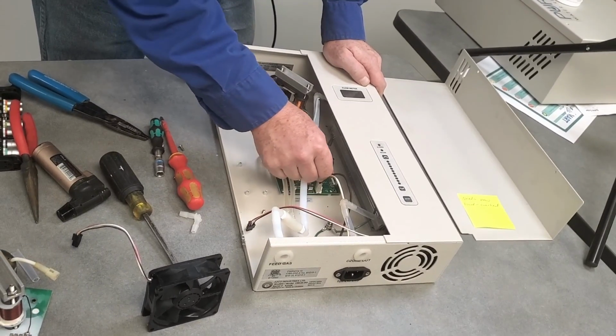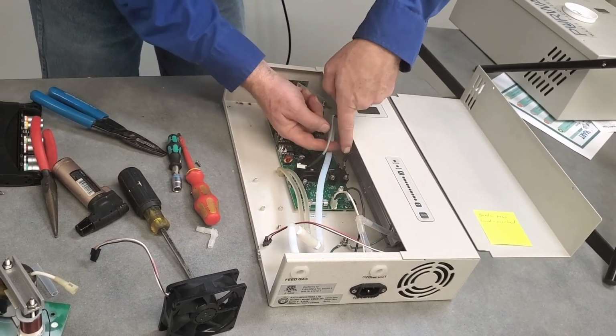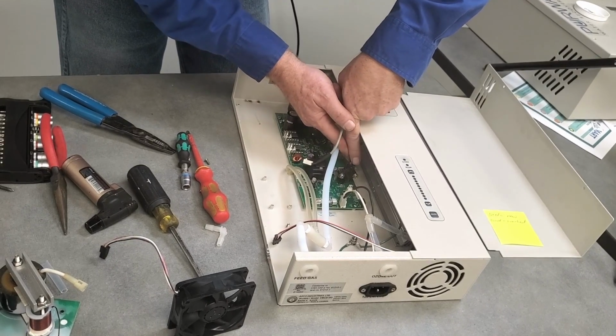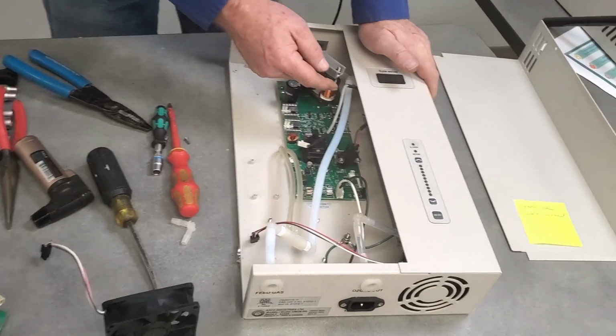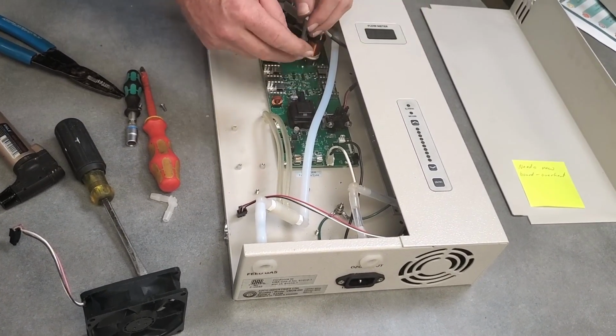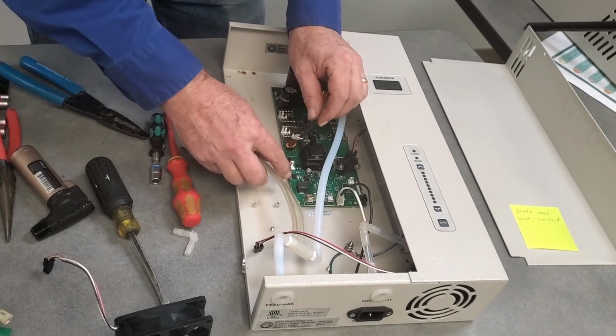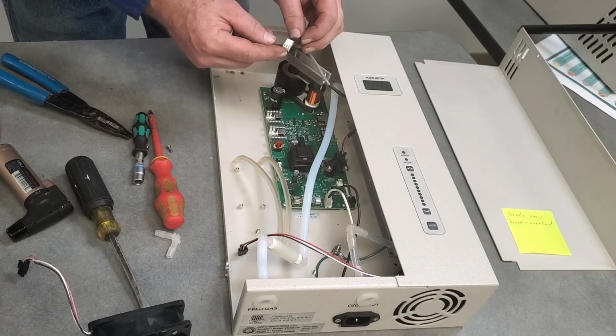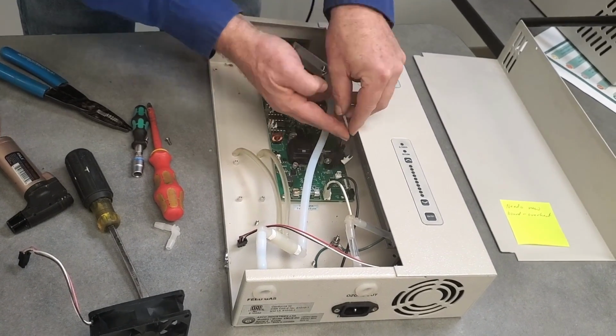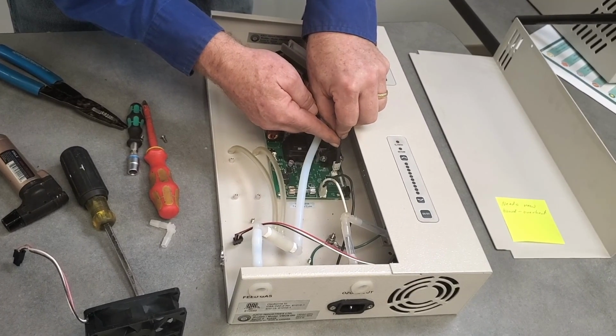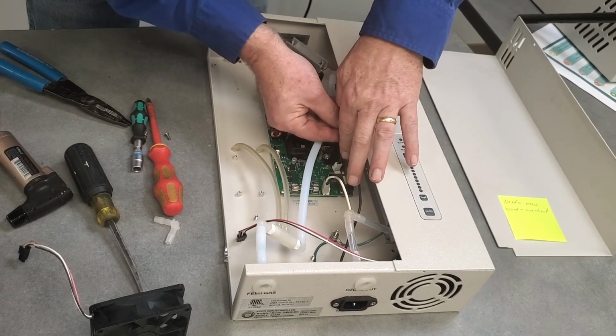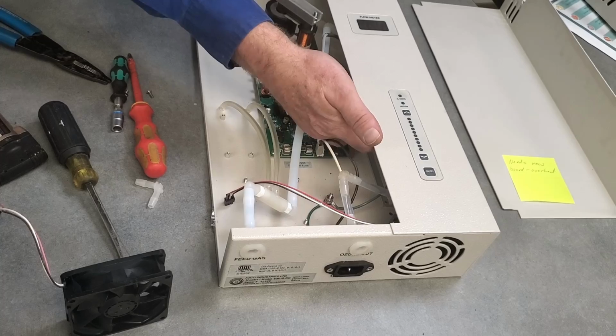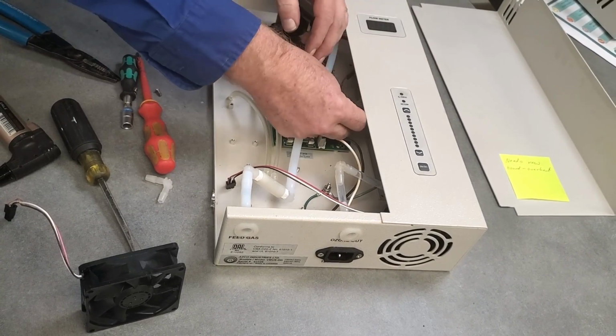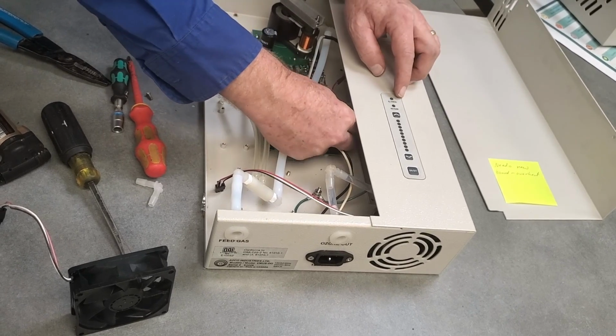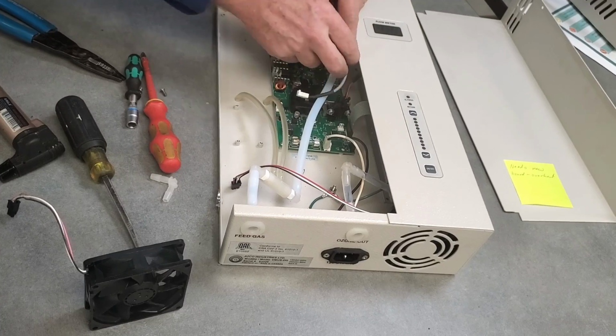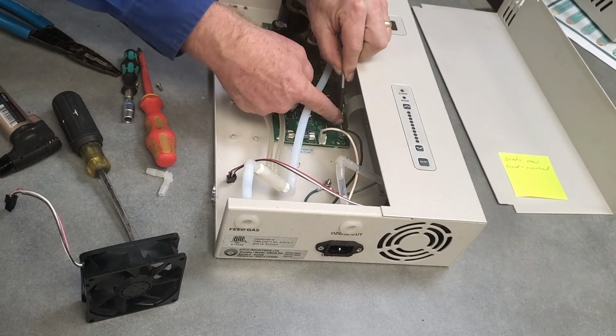Continuing on with this repair here, we've got the board in. We just need to connect a few things here. This is a temperature sensor. It's supposed to turn the board off if it gets too hot. This here is for the flow meter display. It's got 3 contacts, so that plugs in over here. And before I do that, I'll get this ribbon cable. It's tucked up here. Ribbon cable is for this display here, and the flow sensor.